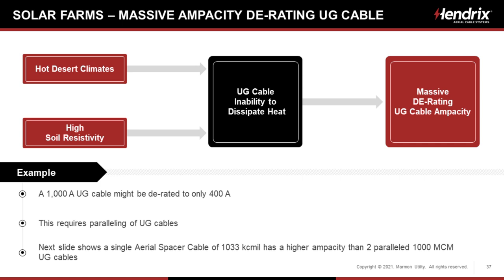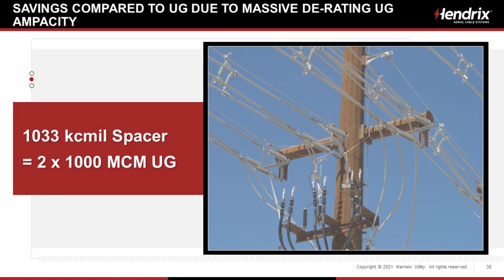So if you take a look at a 1,000 amp standard underground cable, that's going to be derated to maybe 400 amps. So I'm buying a 1,000 amp cable that's good for 400 amps. So that's going to require me to parallel those cables.